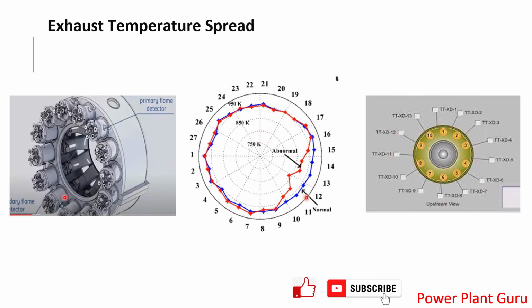There is no temperature measurement in the combustion zone; the gas goes through it and then passes to the turbine, and there is a temperature measurement area at the exhaust. So you will not know the temperature in between, but at the exhaust of the gas turbine you will be able to understand the temperature.